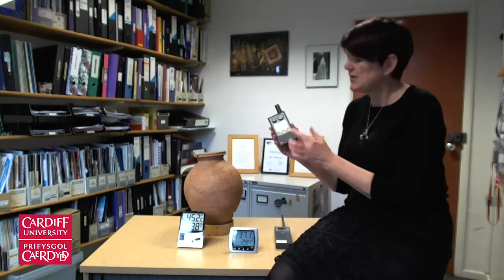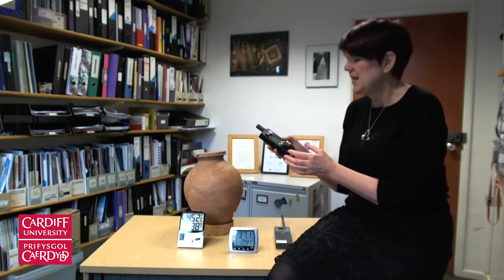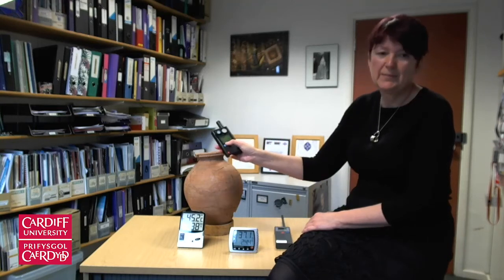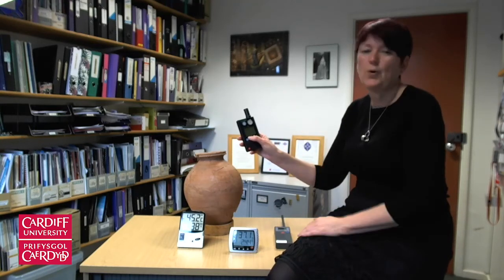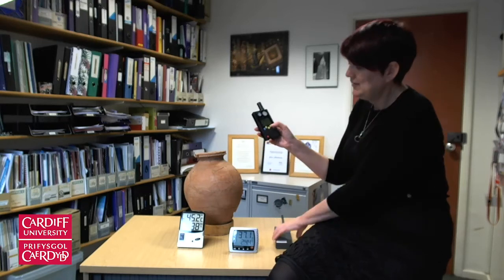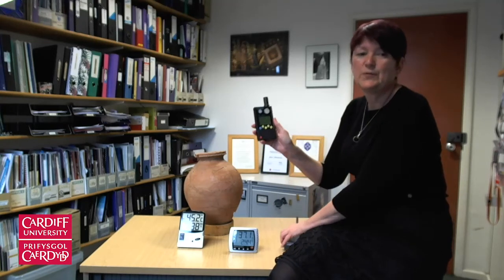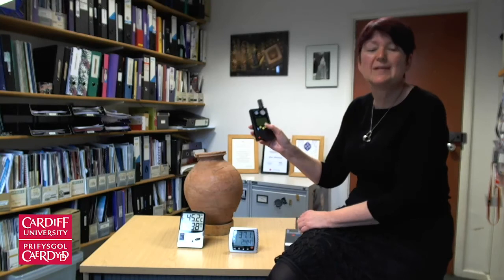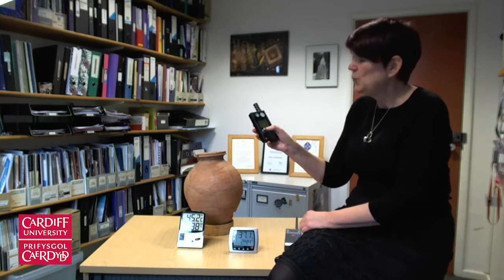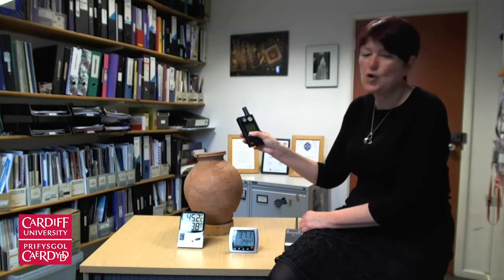You may have access to one of these more integrated meters which have light, ultraviolet light and humidity. These also work in a similar way that you point them in. They also come with a calibration device that you can put on the end. The main difference between these two is that this one's default setting is to take the spot reading the moment you switch it on. And if you want it to continuously read, you have to press and hold until you get the diamond pattern.